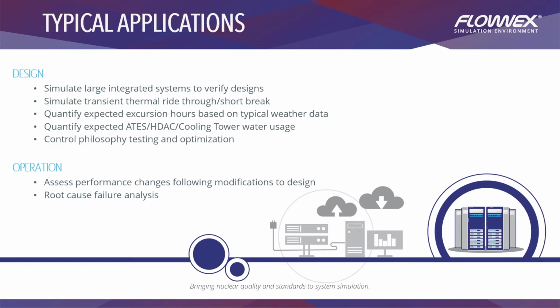Additionally, the instrumentation in data centers is often limited to key locations. So root cause failure analysis can be performed using the software by failing specific components in a simulation and then comparing the results in the software to the results at the key locations where you have measurement data, to try and understand what component failure resulted in the actual system failure that you experienced.